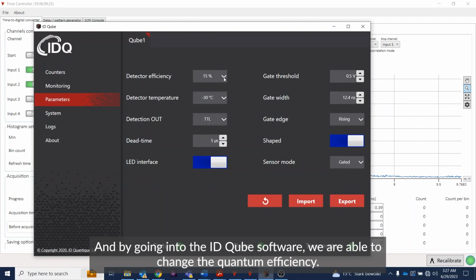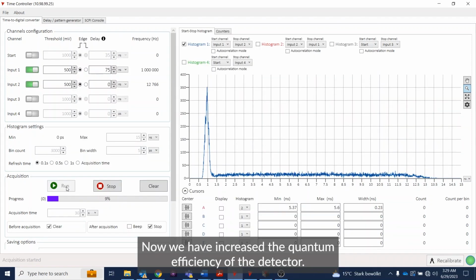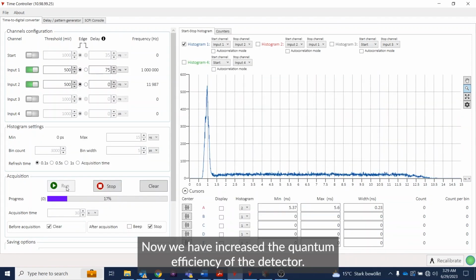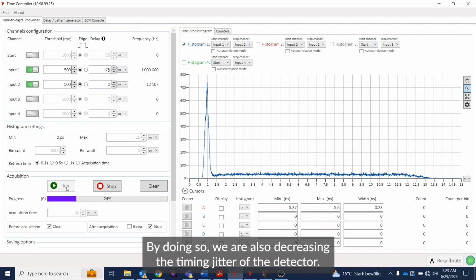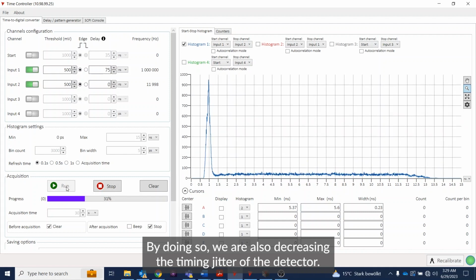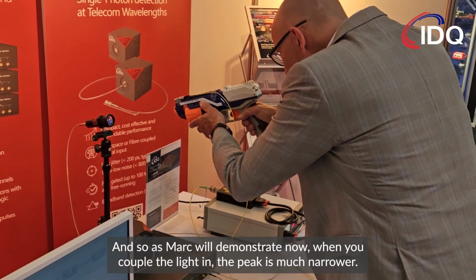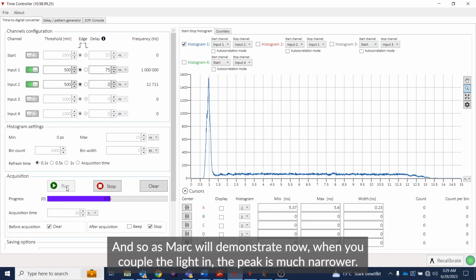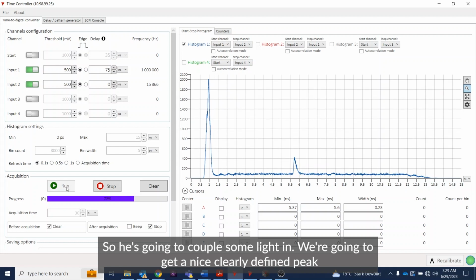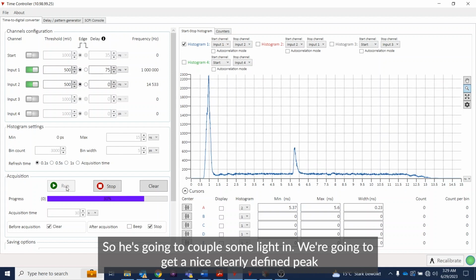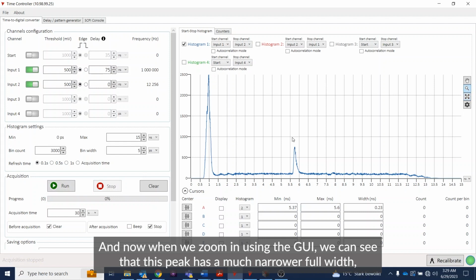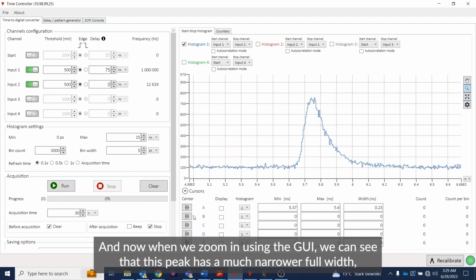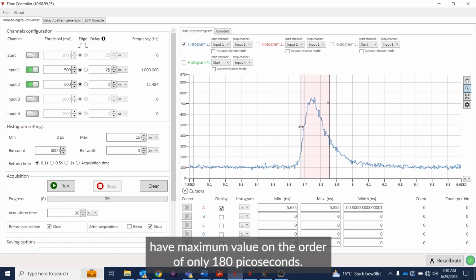And by going into the ID Qube software, we are able to change the quantum efficiency. So now we have increased the quantum efficiency of the detector. By doing so, we are also decreasing the timing jitter of the detector. And so as Mark will demonstrate now, when you couple the light in, the peak is much narrower. So he's going to couple some light in, we're going to get a nice clearly defined peak. And now when we zoom in using the GUI, we can see that this peak has a much narrower full width half maximum value on the order of only 180 picoseconds.